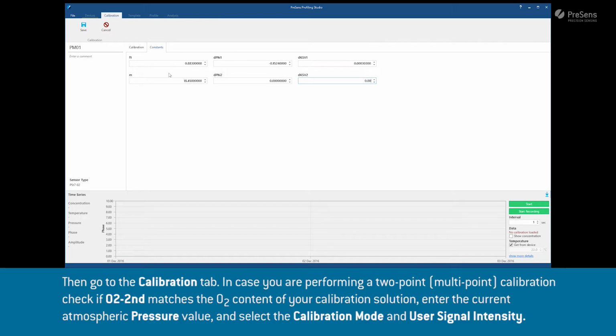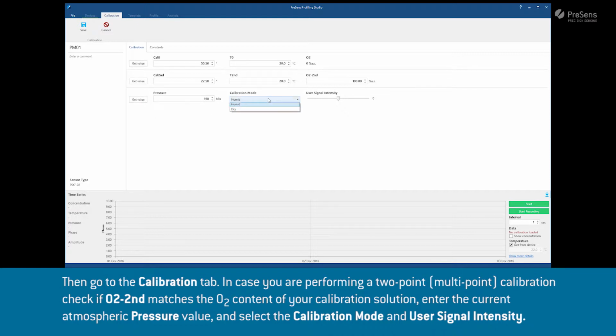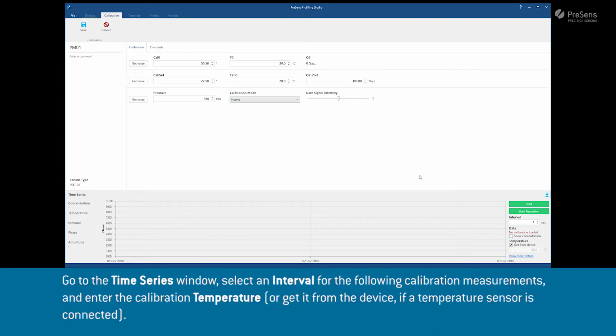Then go to the Calibration tab. In case you are performing a 2-point calibration, check if the O2 second matches the O2 content of your calibration solution. Enter the current atmospheric pressure value and select the calibration mode and user signal intensity. Go to the time series window, select an interval for the following calibration measurements and enter the calibration temperature, or get it from the device if a temperature sensor is connected.